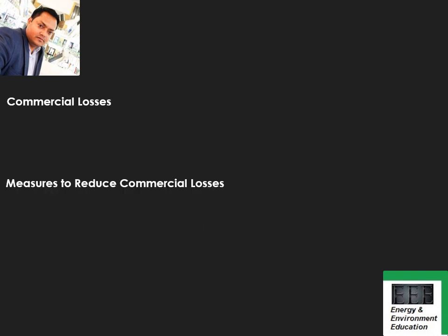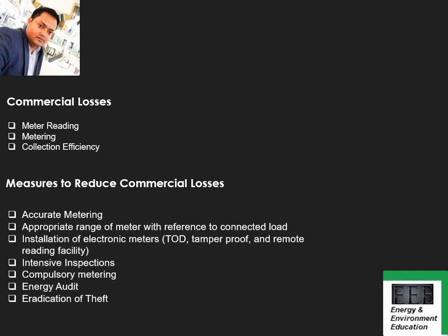As far as commercial losses are concerned, there are three types: meter reading errors, metering issues, and collection efficiency problems. Measures to reduce commercial losses include: accurate metering, appropriate range of meter with reference to connected load, installation of electronic meters with TOD, tamper-proof, and remote reading facilities, intensive inspections, compulsory metering, energy audits, and eradication of theft. You can refer to the book for detailed explanation.